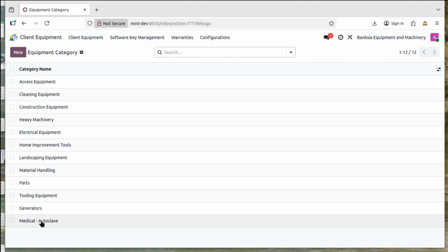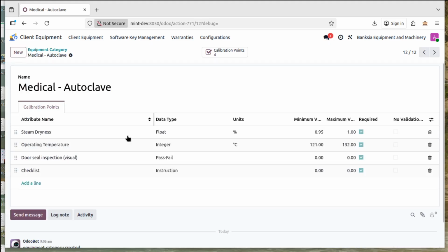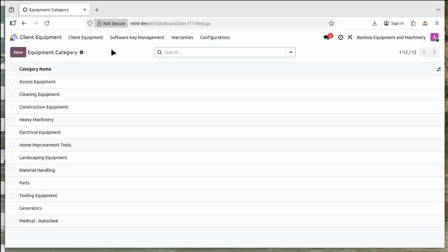I've also got one here for a medical autoclave, and I've got a couple of inspection points on this one too. So the idea is you group together like products that require similar sorts of calibration tests, and then you merely put it in the right category and it automatically inherits the right tests that need to be carried out on that particular equipment. So let's go and see one that we've done already.